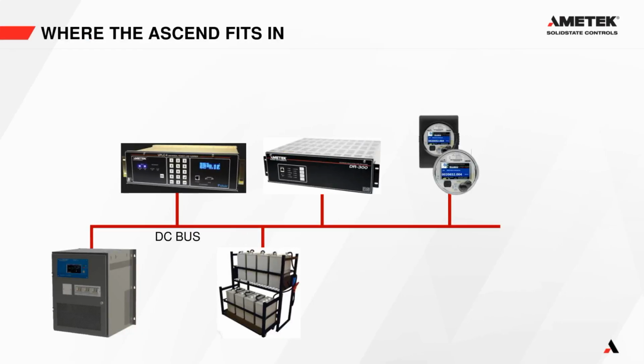All right, so we're going to talk about the Ascend charger, which is a new battery charger for us. We sell it in a 3-phase AC input variation and a single-phase variation. So the one I'm going to talk about today is the 3-phase input. It's supposed to fit into a substation or a control room or a petrochemical plant. It will supply power to a DC bus that then can be used for controls, metering, and then it also usually connects to a battery, so for backup reasons.